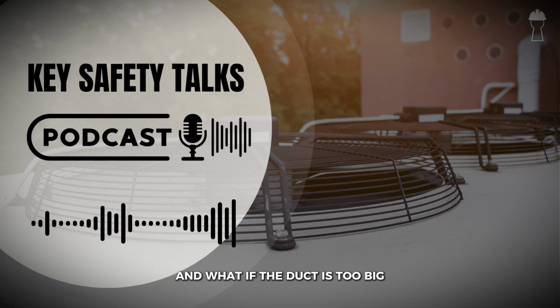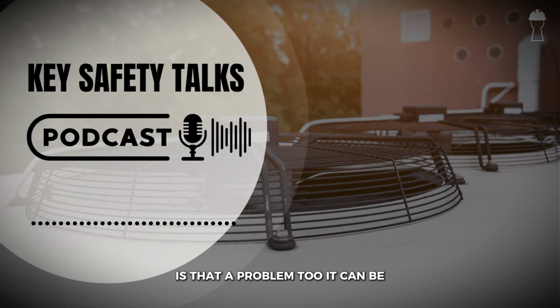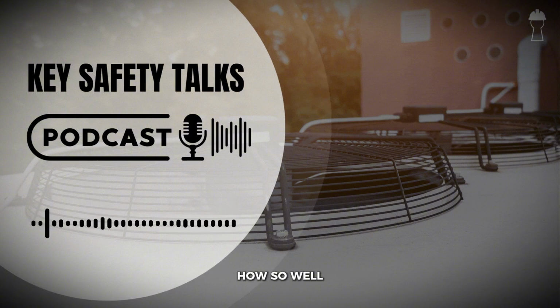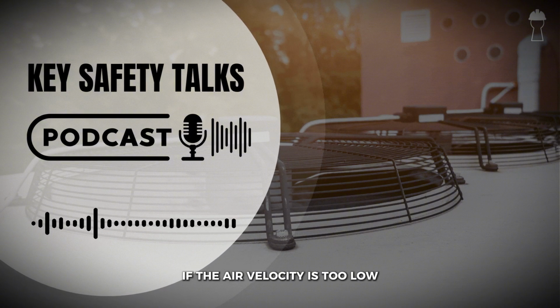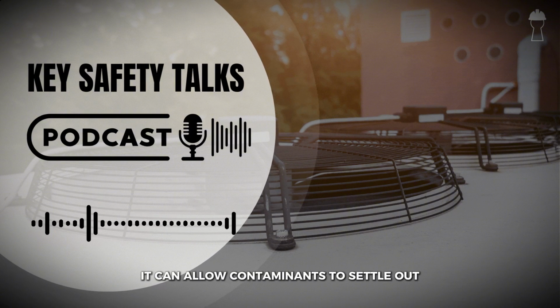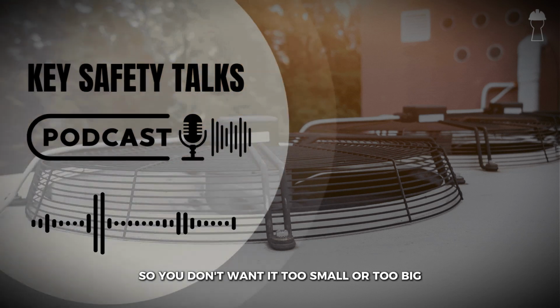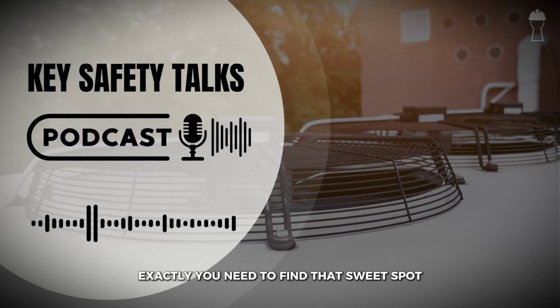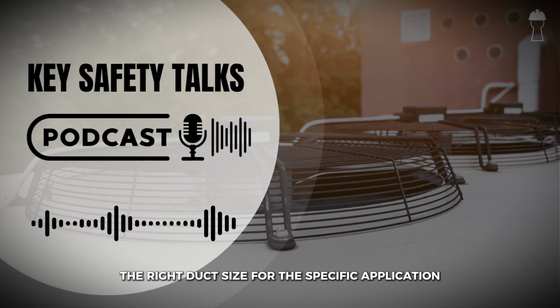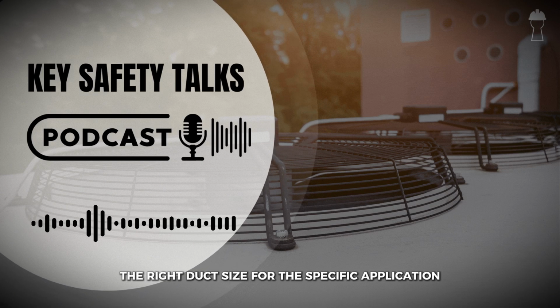And what if the duct is too big? Is that a problem too? It can be. How so? Well, if the air velocity is too low, it can allow contaminants to settle out and accumulate inside the ductwork. So you don't want it too small or too big. Exactly. You need to find that sweet spot, the right duct size for the specific application.